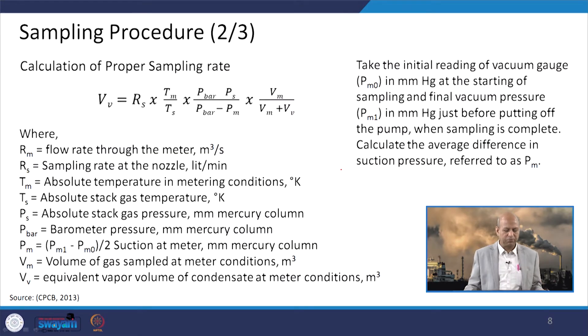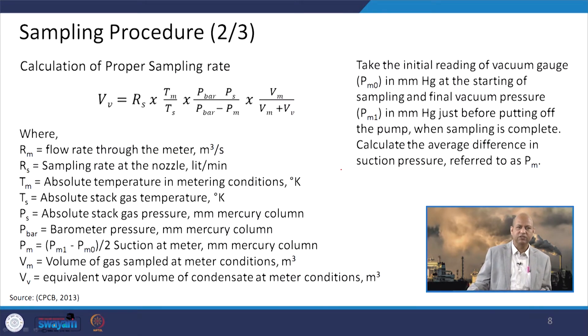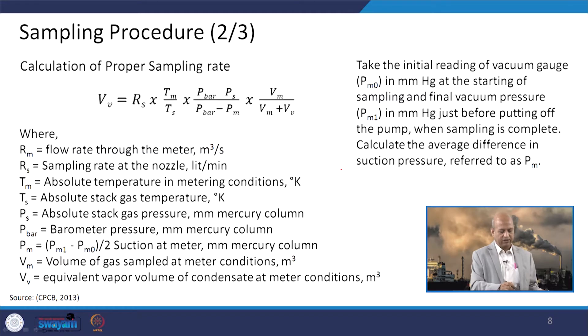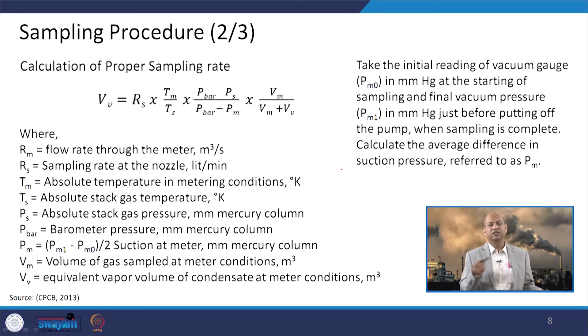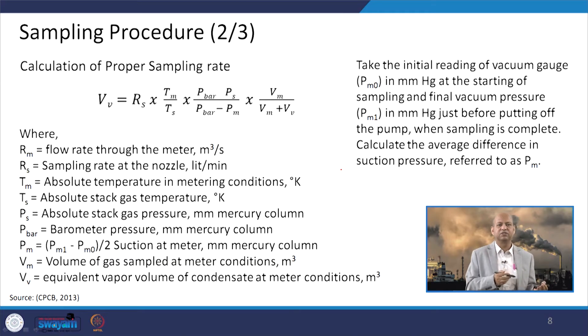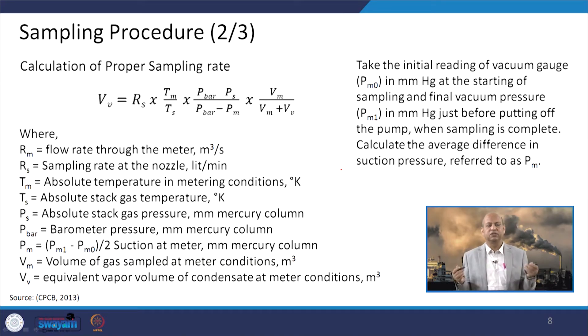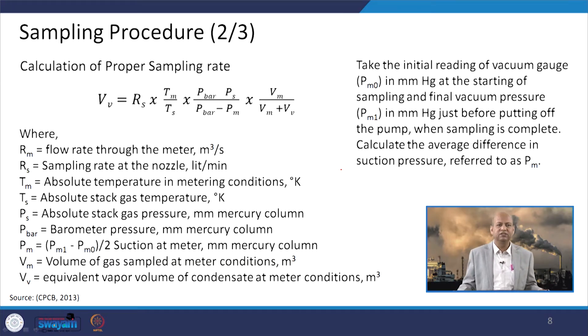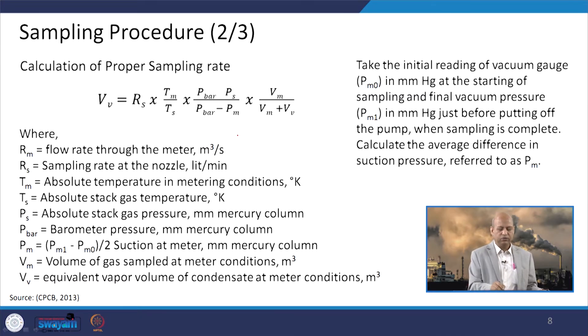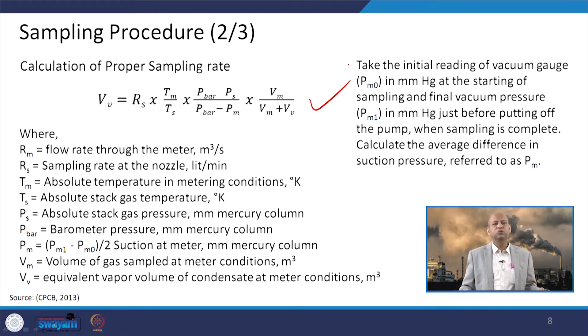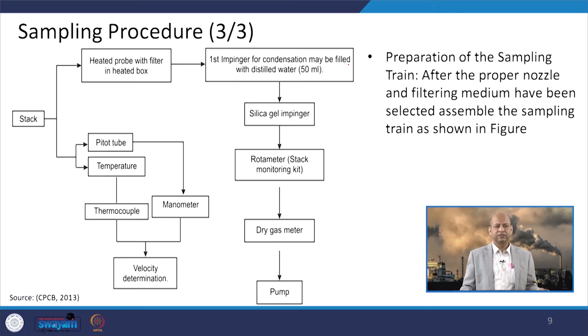Calculation of the proper sampling rate is also very important, done with the help of a gas meter for each sampling point before starting the test. Different parameters are used in this calculation procedure: flow rate, sampling rate, absolute gas temperature, absolute temperature of the metering conditions, and barometric pressure — all these parameters are noted and used in the equation to calculate the sampling rate.